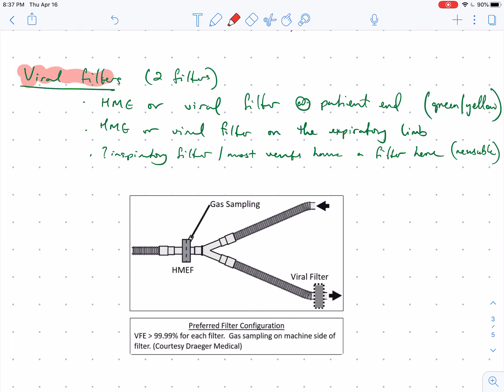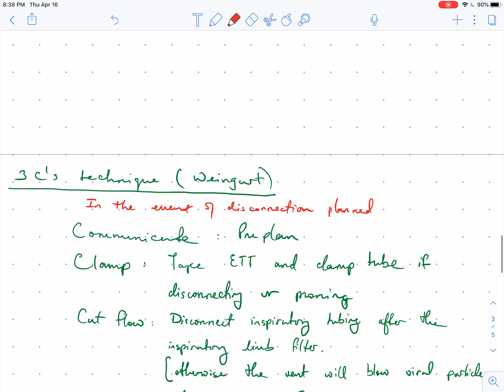We know about the viral filters. It's very common to us, and most practitioners would know about it. But for COVID, you want two filters set up. So your HME or viral filter at the patient end, usually a green-yellow filter, and another HME or viral filter on the expiratory limb. So that's a two filter setup. Now, there's a question whether you need an inspiratory filter. Most vents do already have a reusable filter there. And remember, for these filters, the viral filtration efficacy must be more than 99.9%, for example, the Intersurgical type HME filters.